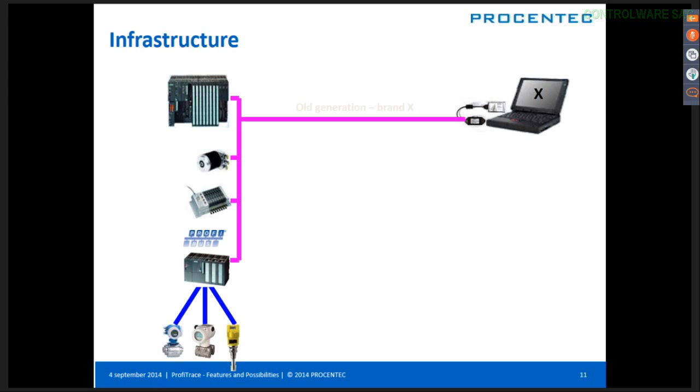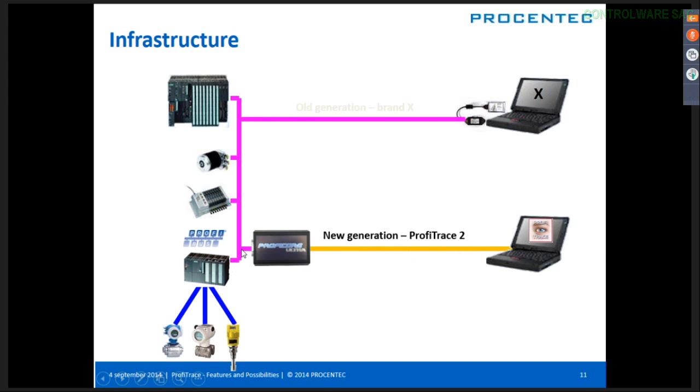Okay, so in the older days we had this PCMCIA card. Nowadays we have these Siemens laptops. Most of them are using them. But in the older days we had this PCMCIA card, and we created our Proficore because you needed to connect this PCMCIA card by a long stub line. This Profibus line is a long stub line. So that's why we have created our Proficore, to create a short stub line and go by USB to our laptop. Well, it depends a little bit on how much power, but your USB cable may be 5 meters.